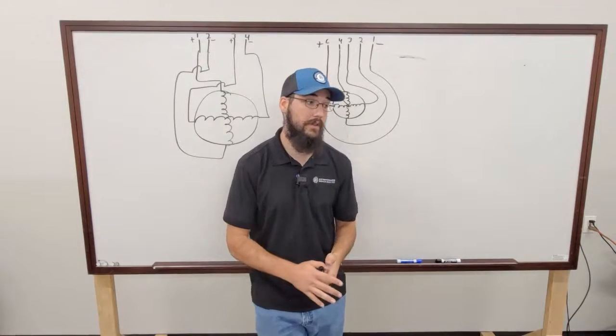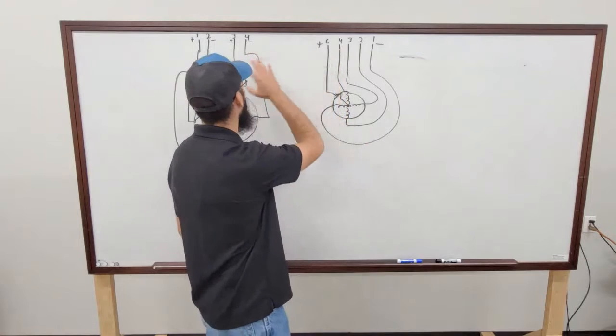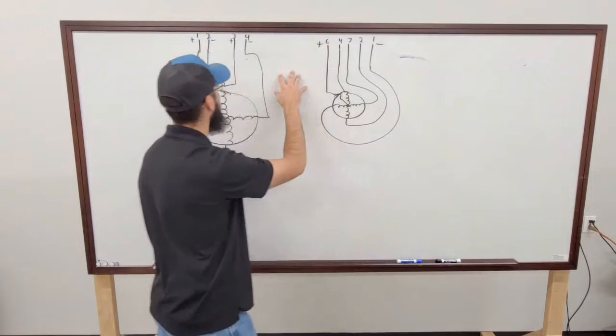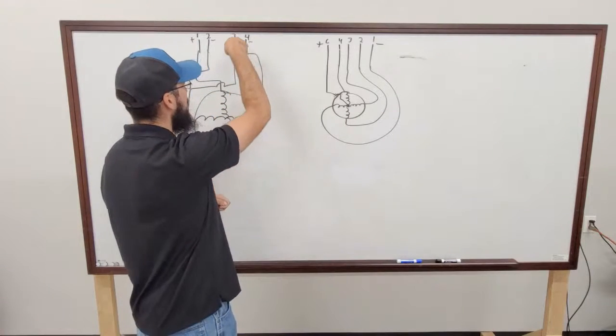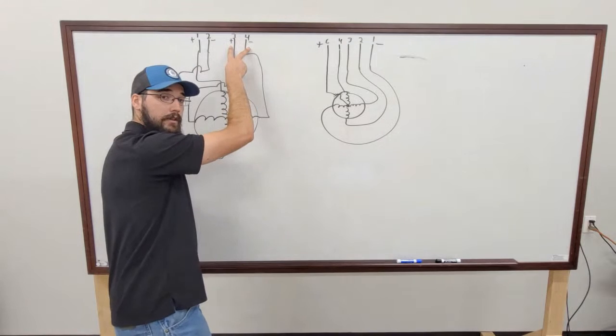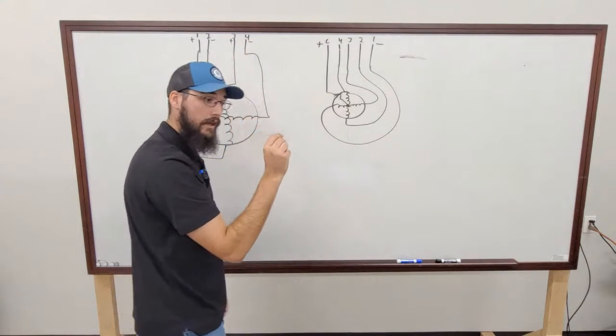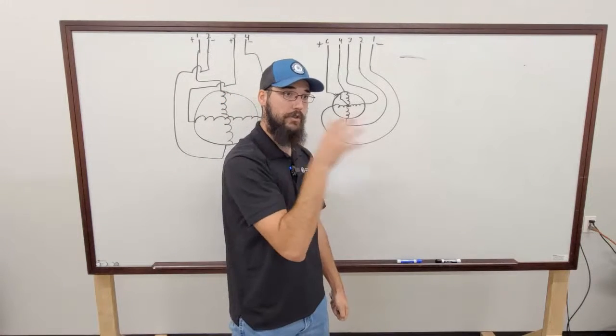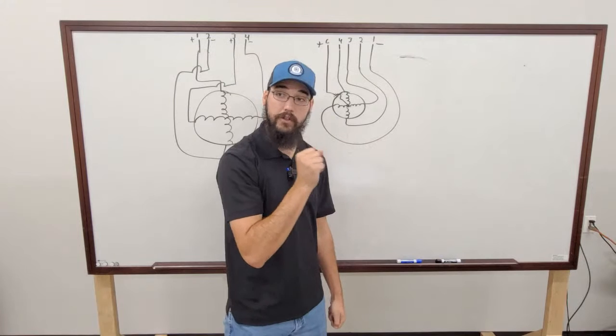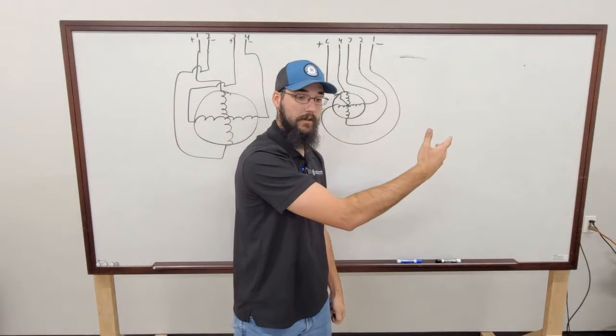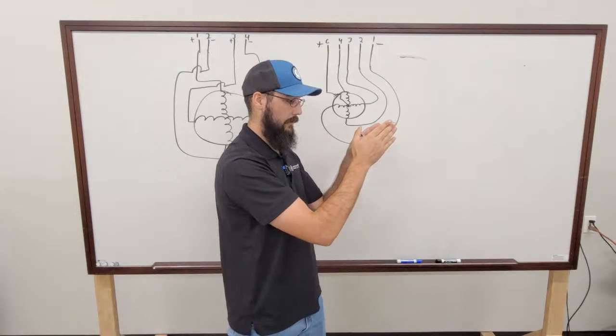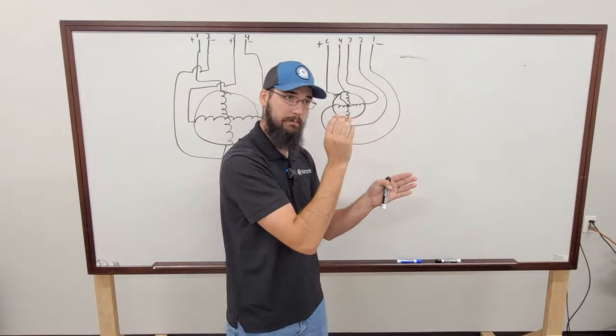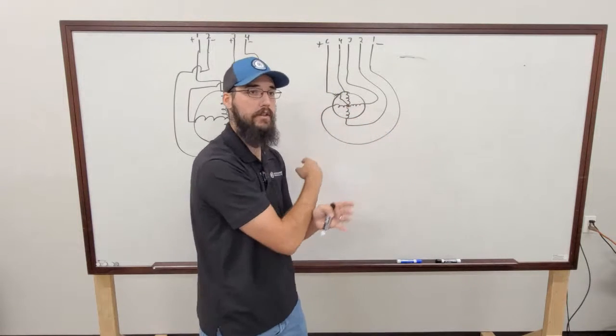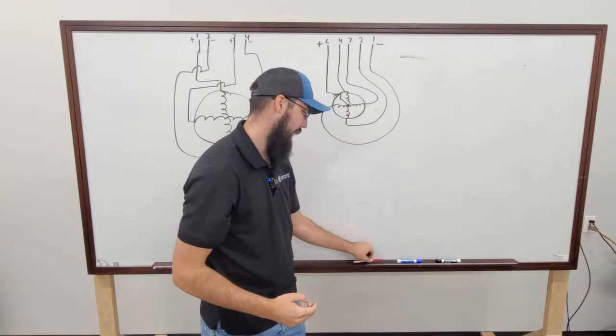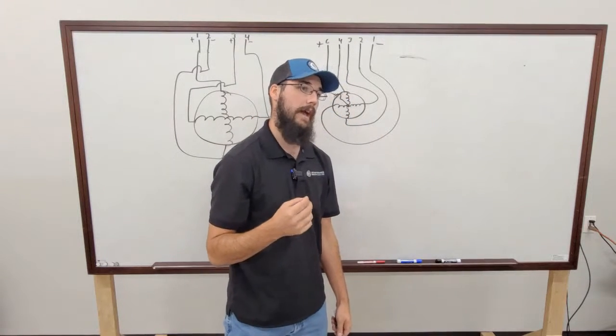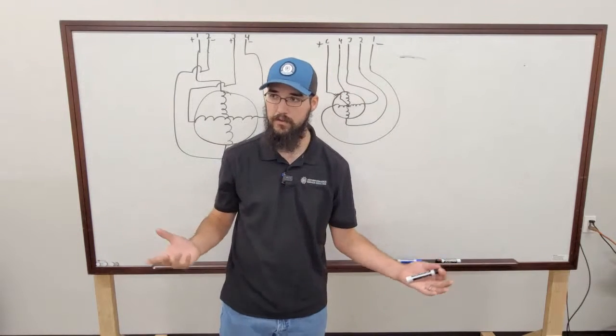Now, something you would see, if you were questioning if the controller was working properly, you should be able to unplug these, put your leads on the harness side from the controller on, say, 3 and 4, and your meter, once you actuate it, you should see your meter flashing. That's a good thing. That means it's cycling the pulse. Yeah, it's pulsing that winding, and then you could check the other side. Now, most of the time that happens so fast that the meter has a hard time getting a real reading, so you can't verify the voltage that way.